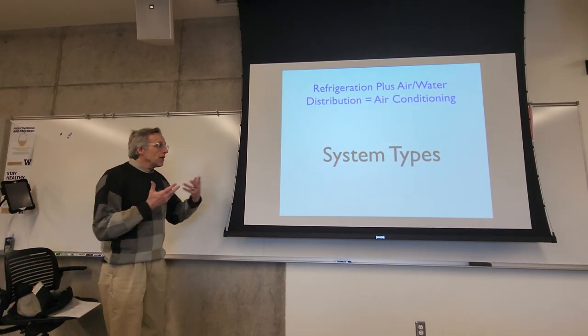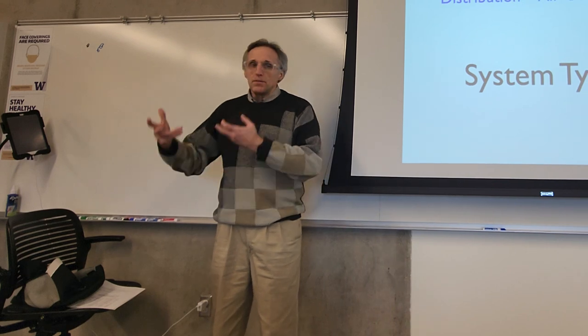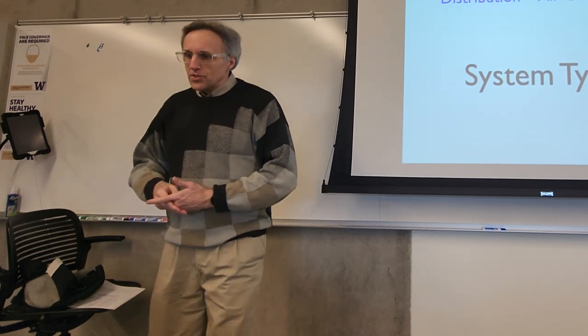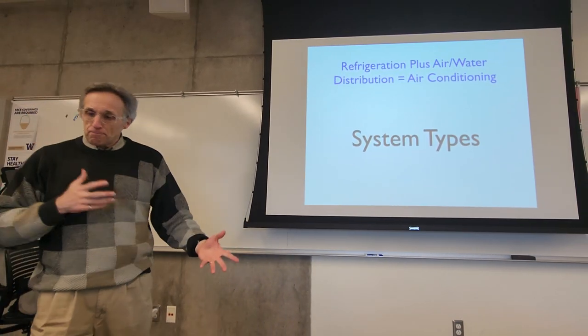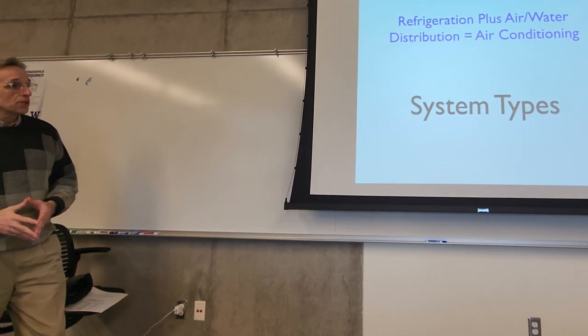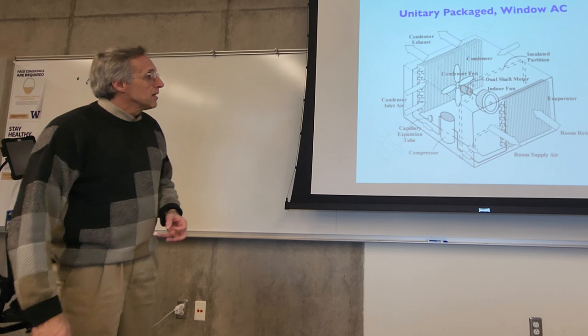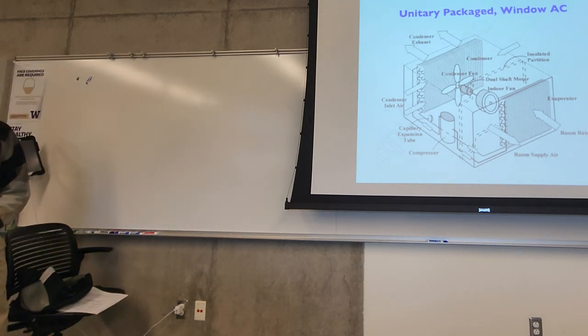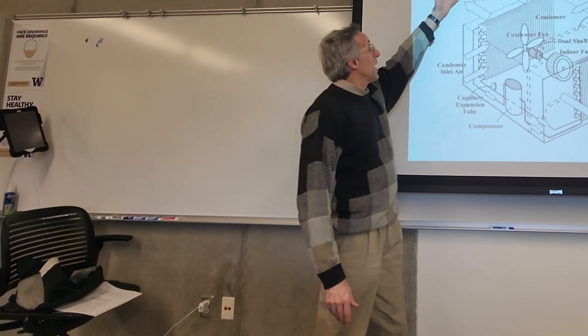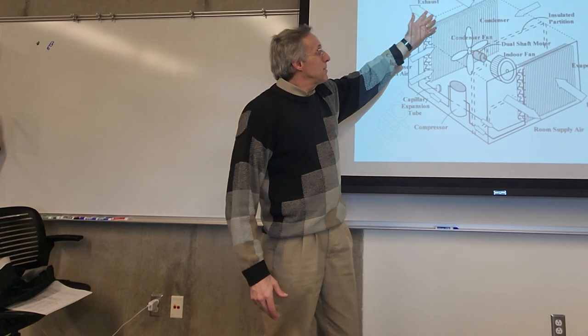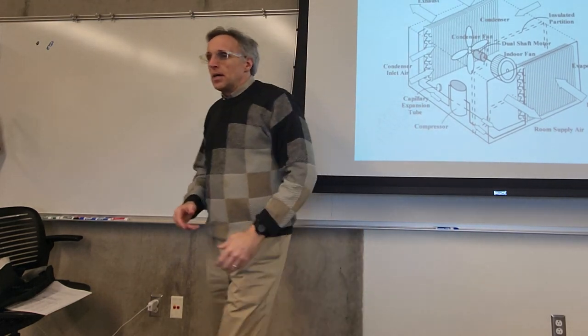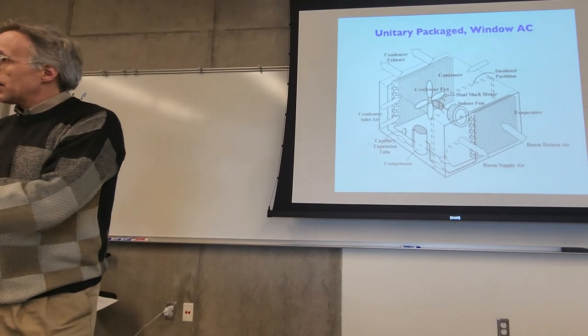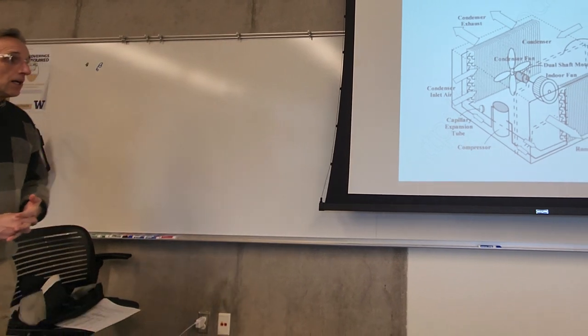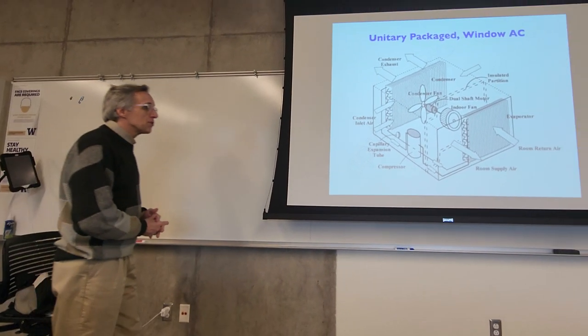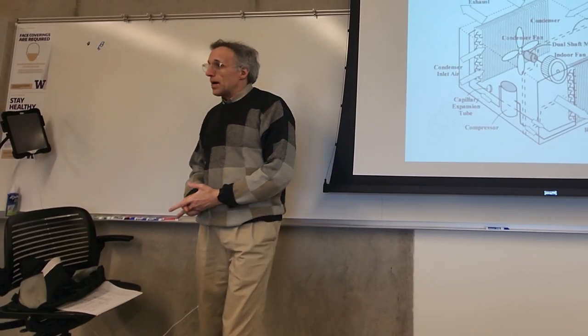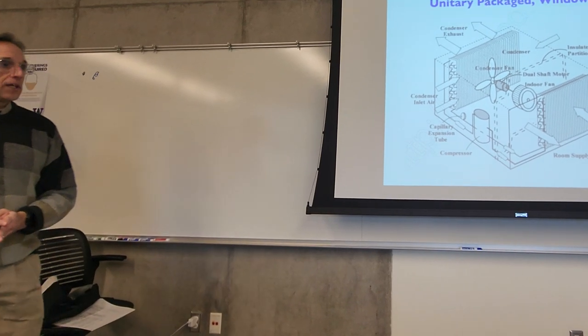Now, just looking at different ways that we mate the refrigeration cycle to the rest of the air conditioning system. So refrigeration plus the air handling, and in some cases, water handling and distribution. So we're going to look at some general system types here. The simplest being the window air conditioner. The window air conditioner is part of a larger category called unitary packaged systems. Unitary just means everything is in one box. That means the refrigerator plus the fans and air handling and everything all in one. These are great for single room applications, maybe a couple of small rooms, up to about 12,000 BTU, half a ton to 1 ton.